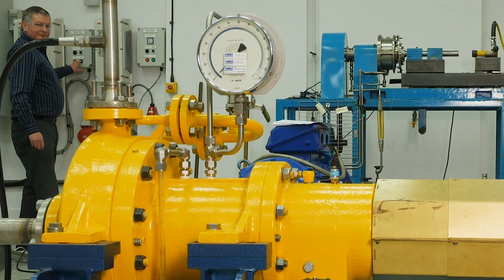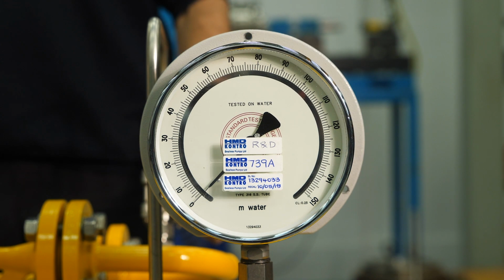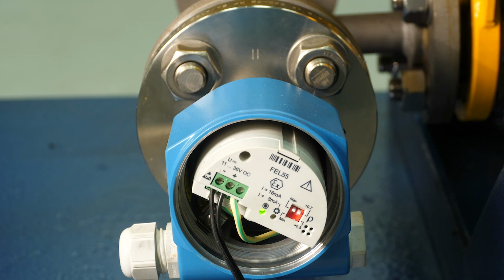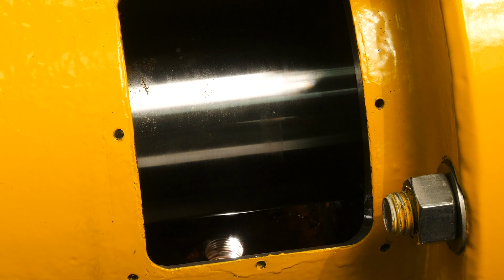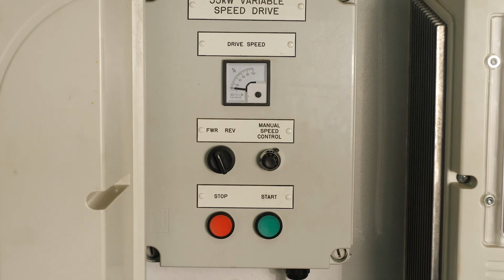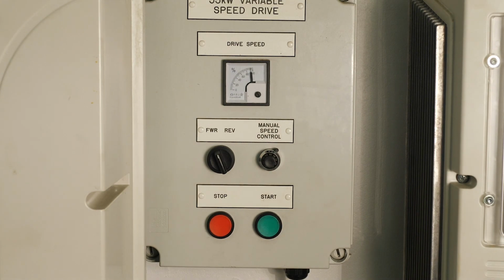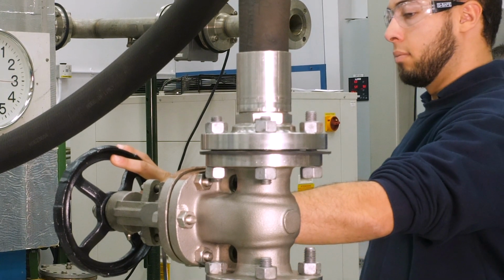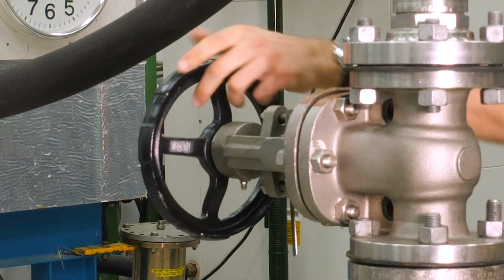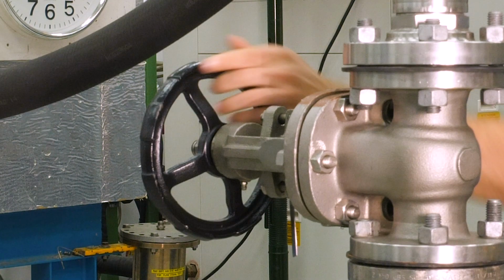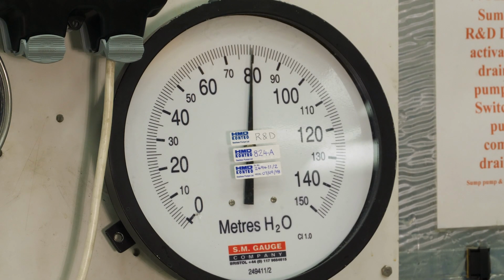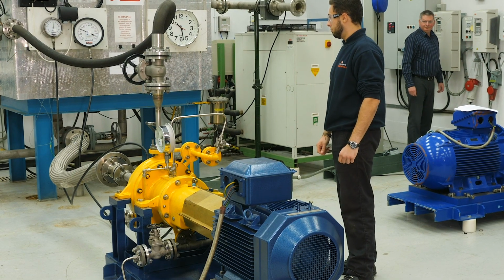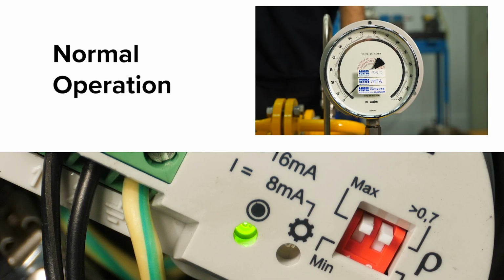A pressure gauge monitors the pressure in the coupling housing, which in atmospheric air reads 0. A liquid level probe is also positioned to detect the presence of liquid in the secondary pressure housing. A hole is positioned at the bottom of the bearing housing. The magnetic drive pump is switched on, running at 2 pole speeds. The magnetic drive pump is piped to a water test tank with the valve on the discharge pipe providing a system resistance, and the discharge valve is adjusted to set an 80-meter discharge head. In normal operation, the secondary housing pressure reads 0, and the green LED on the liquid level probe indicates that it is operational but not activated.